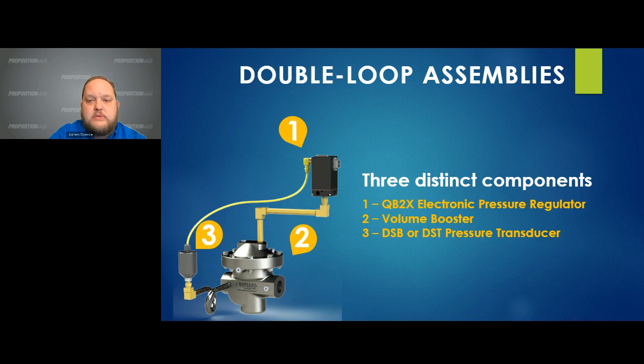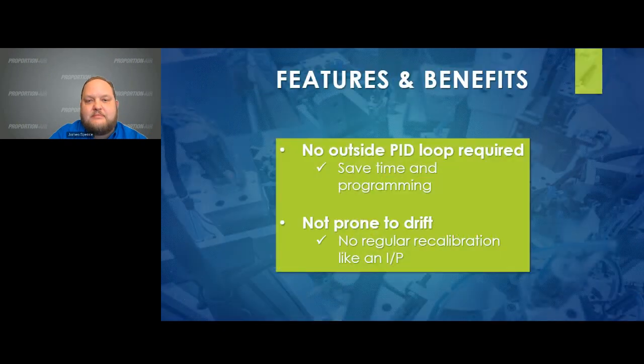A pressure transducer is added to the assembly to measure the output pressure of the volume booster. This provides a feedback signal to the QB2. The QB2 adjusts the dome pressure based on this feedback to achieve the commanded pressure in the process. Even with a full assembly, we still maintain plus or minus 0.5% accuracy, pardon me. While an assembly may look complicated, they're basically plug and play.